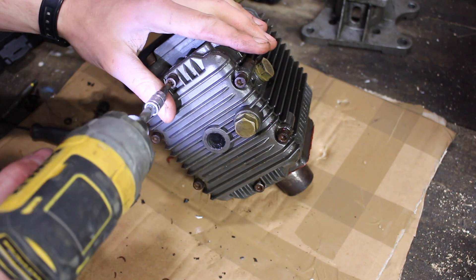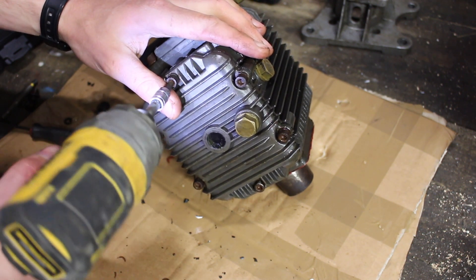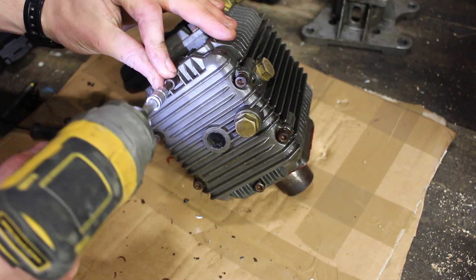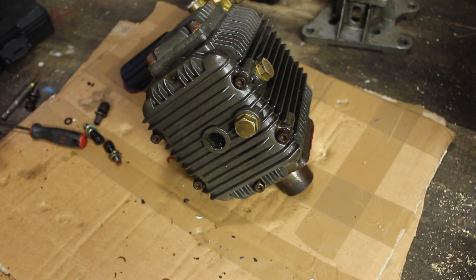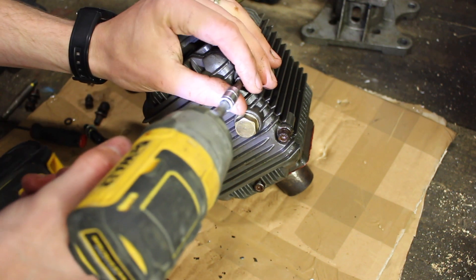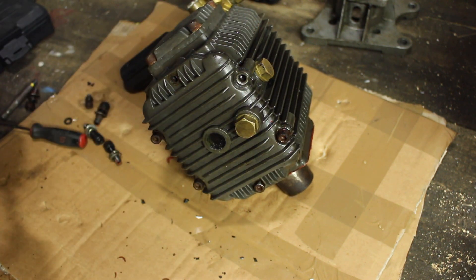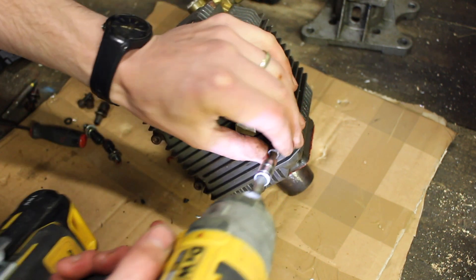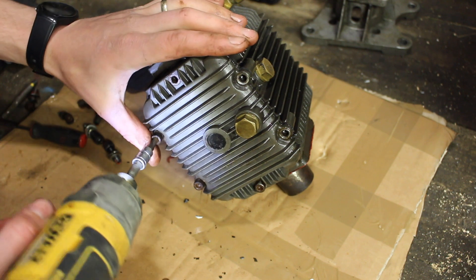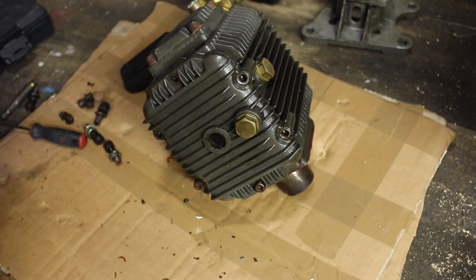There's no oil in this pump anymore, so I can remove the end plate and we can take a look. My guess is it's going to be one of the conrods or maybe one of the bearings — something has either bent, seized, or broke due to lack of oil.